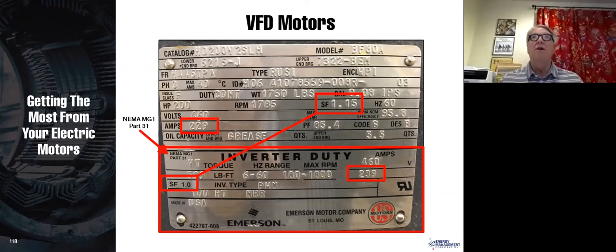So this is the standard for variable frequency drives. If you're going to run a motor on a variable frequency drive, you must always specify a service factor motor, either 1.15, which is the most common, or a lot of motors are 1.25. Our Galt motors, a lot of those are 1.25. But you need at least 1.15 service factor, and that indicates that the motor across the line can actually run 15% over its rating without overheating. But when you put it on a drive, you cannot use that service factor. It becomes a 1.0 service factor.